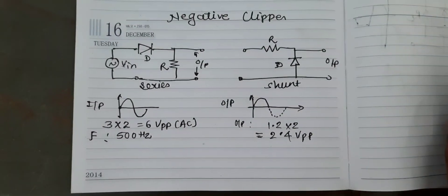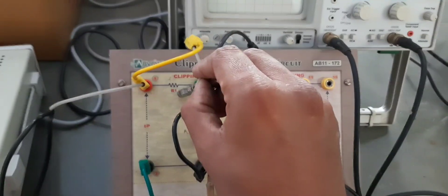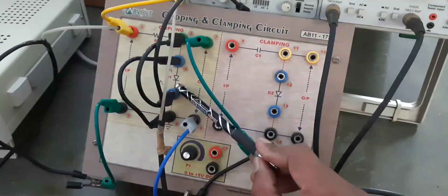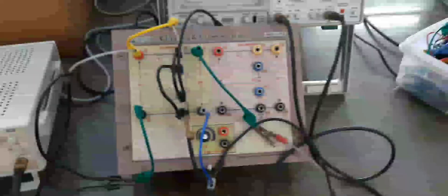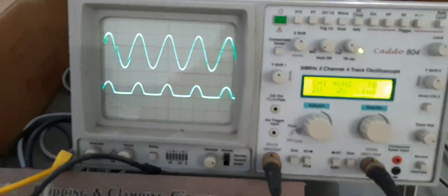There can be a number of reasons for this variation. First, because of the probes we are using, their resistance gets added. Because of the variation in resistance, increase in temperature from continuous use, and the resistance of patch cords and cables getting added, the output is somewhat reduced.